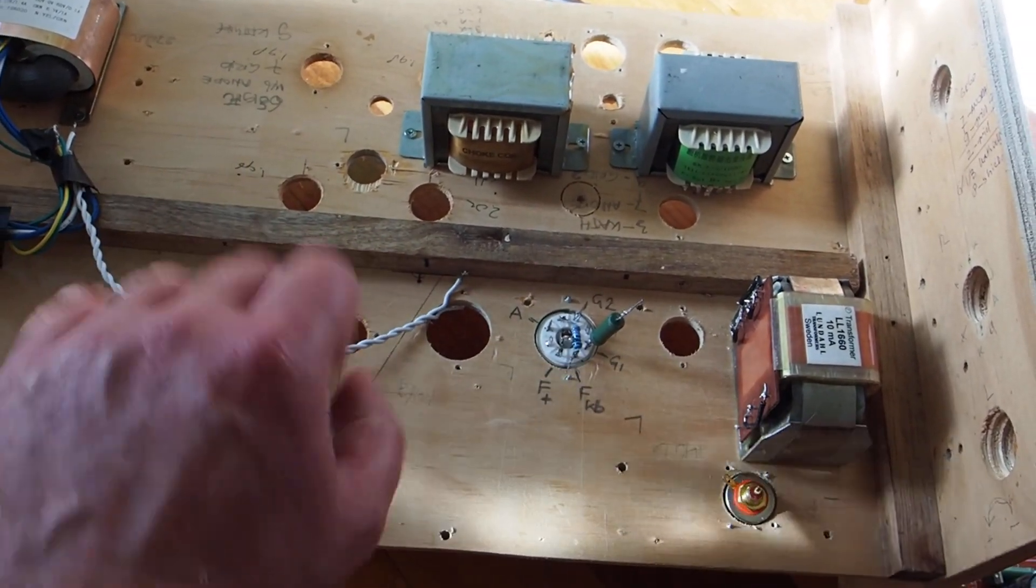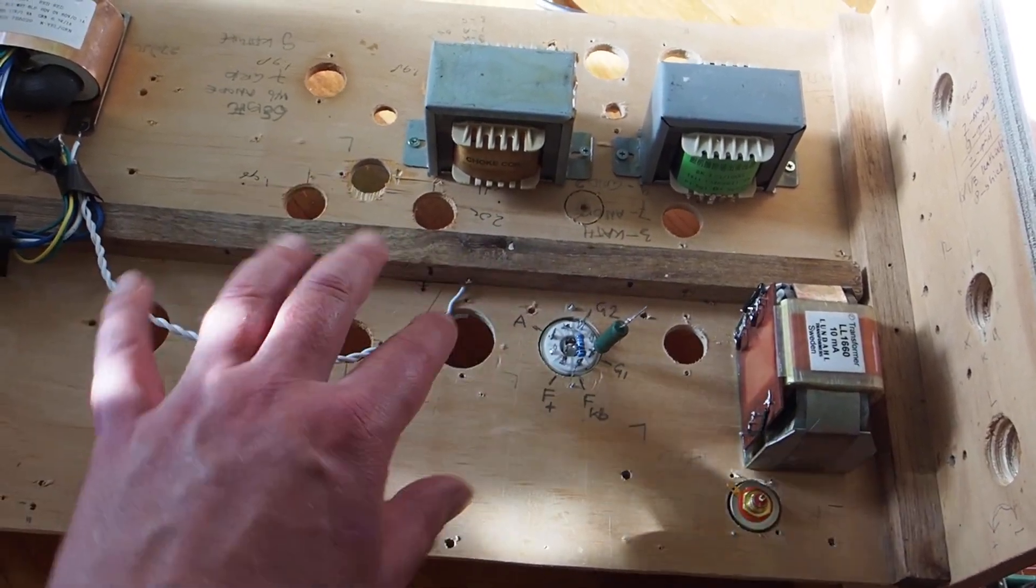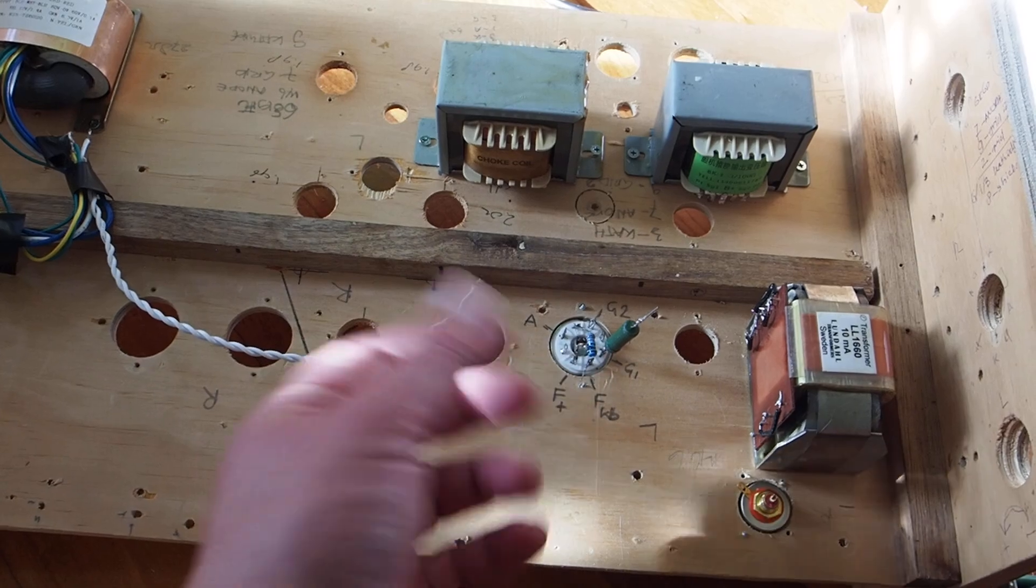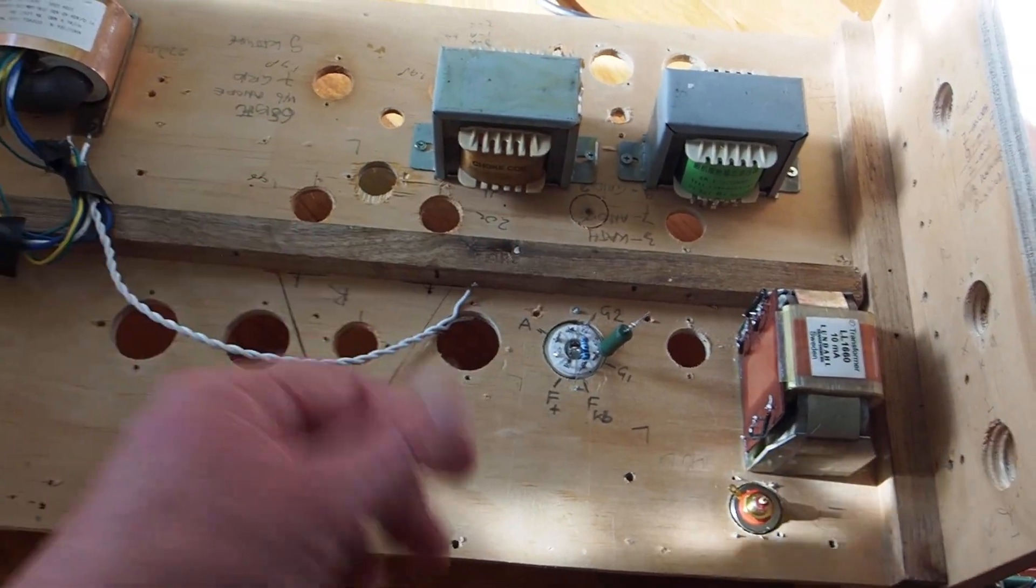And then fourth is the signal wiring. Once I've got all the higher current and AC current things, then I'll put the signal wire in there and I usually crisscross it straight and so on, so there's minimal influence on the signal.